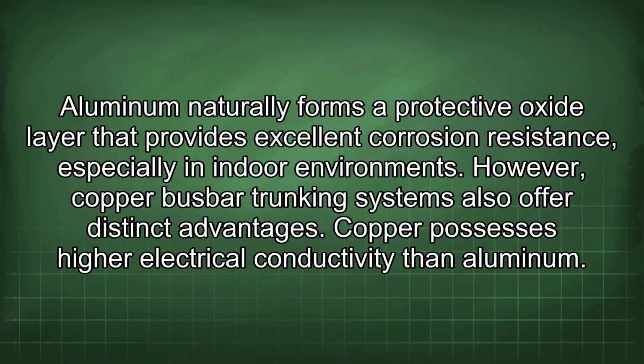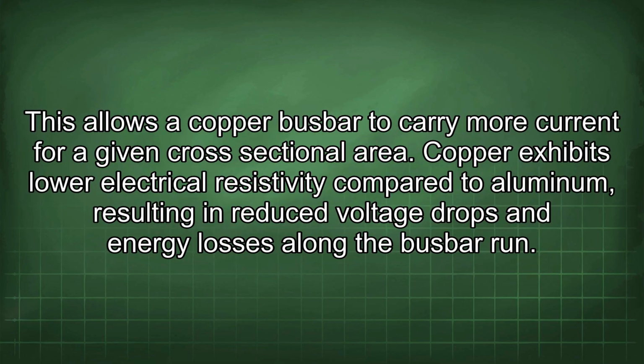However, copper busbar trunking systems also offer distinct advantages. Copper possesses higher electrical conductivity than aluminum. This allows a copper busbar to carry more current for a given cross-sectional area. Copper exhibits lower electrical resistivity compared to aluminum, resulting in reduced voltage drops and energy losses along the busbar run.